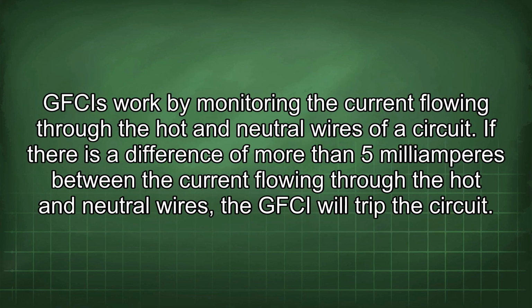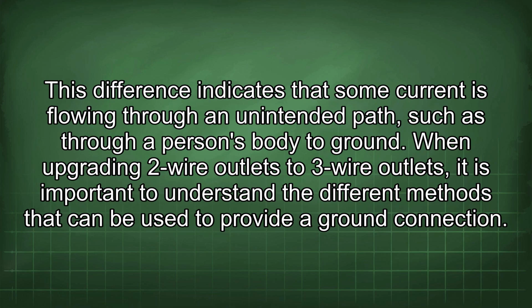GFCIs work by monitoring the current flowing through the hot and neutral wires of a circuit. If there is a difference of more than 5 mA between the current flowing through the hot and neutral wires, the GFCI will trip the circuit. This difference indicates that some current is flowing through an unintended path, such as through a person's body to ground.